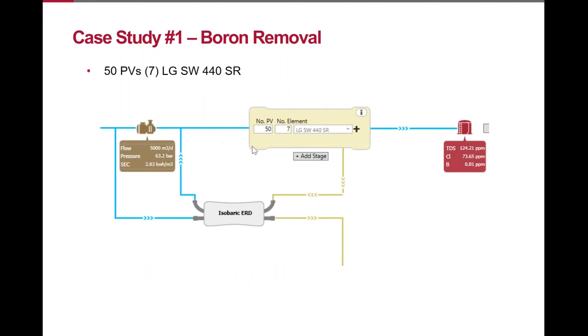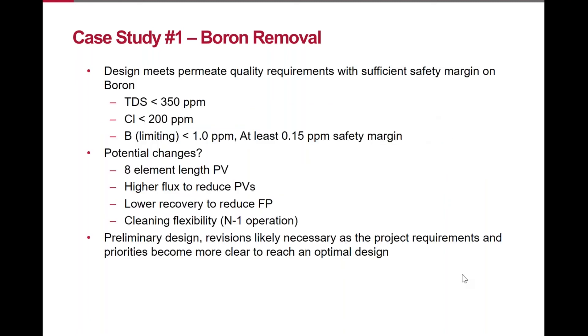Switching back to the presentation summary: the design satisfies TDS less than 350 ppm, chloride less than 200 ppm, and boron — the limiting factor — less than 1 ppm. We also had sufficient safety margin of at least 0.15 ppm, meaning worst-case projected boron was less than 0.85 ppm.